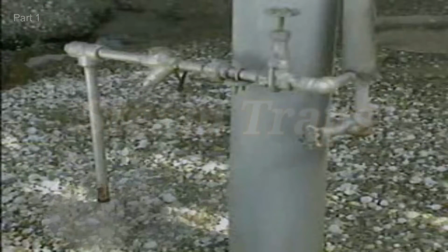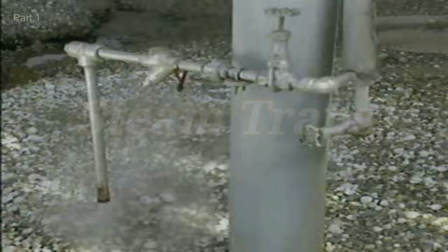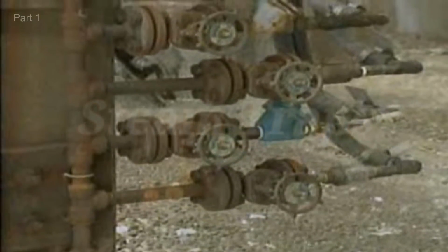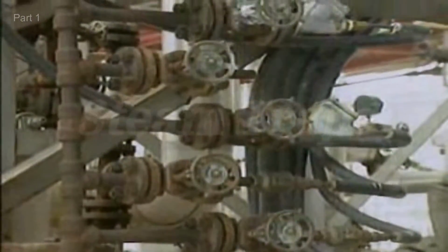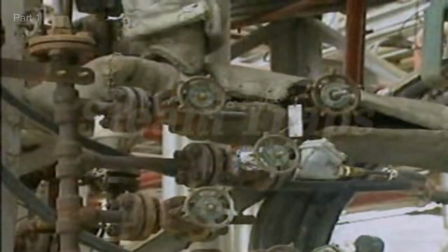To maintain system efficiency, a steam trap must be able to remove condensate, air, and other gases quickly. The trap must also be able to respond promptly to changing conditions in the system. In most facilities, the rate at which steam condenses in a system varies considerably. If the steam traps in the system can't effectively respond to these variations, the traps will either discharge live steam or they'll leave condensate in the steam lines. Both of these situations can create problems and reduce system efficiency.